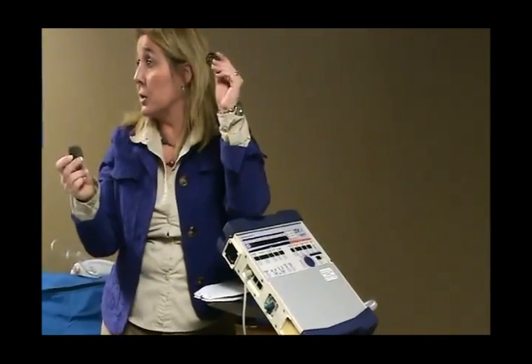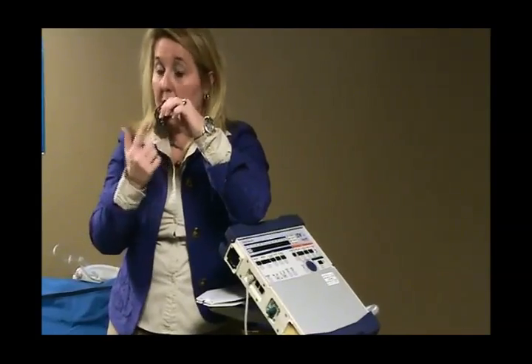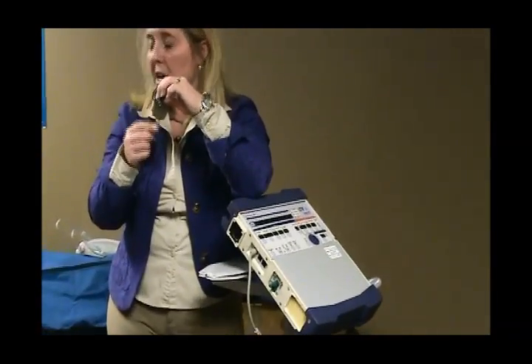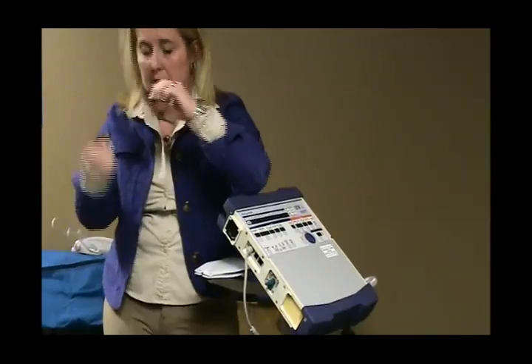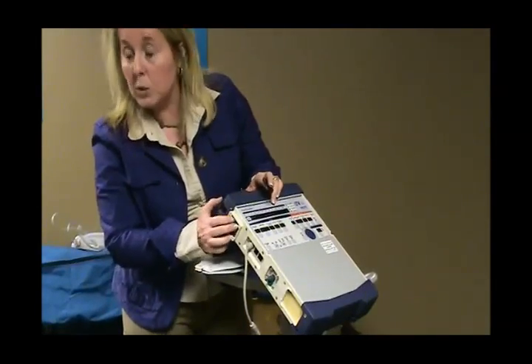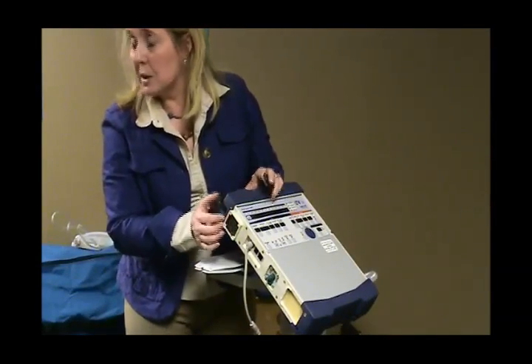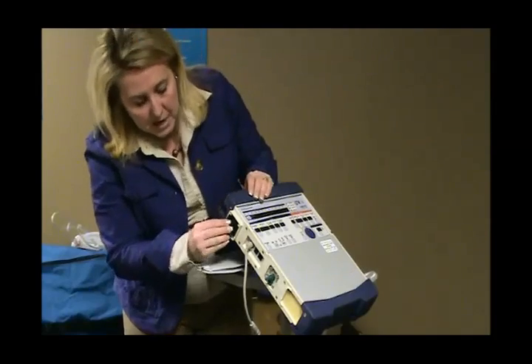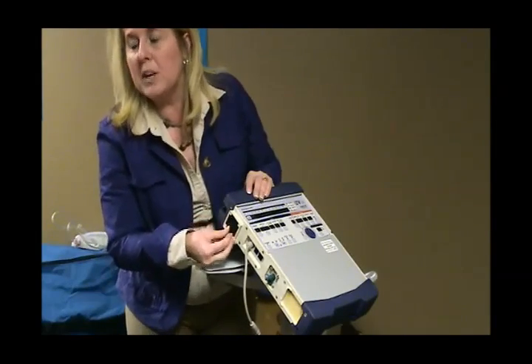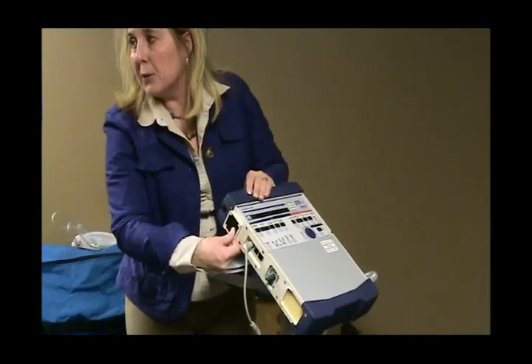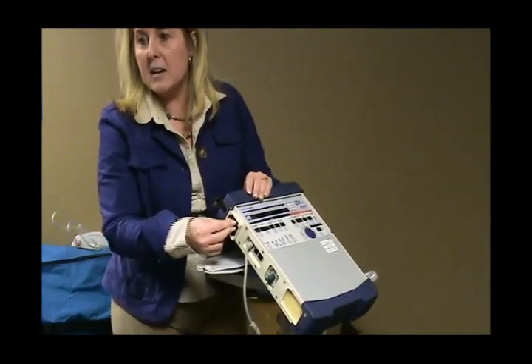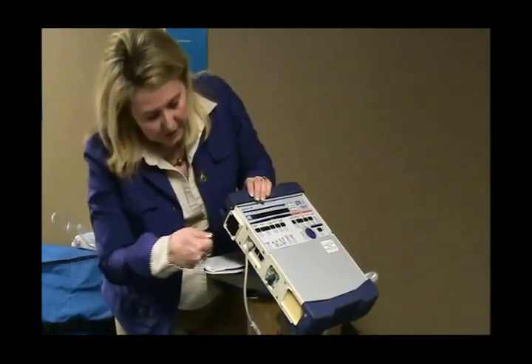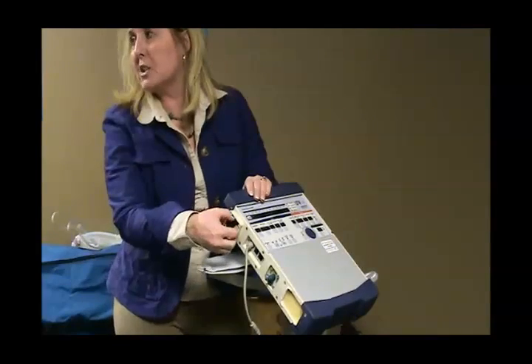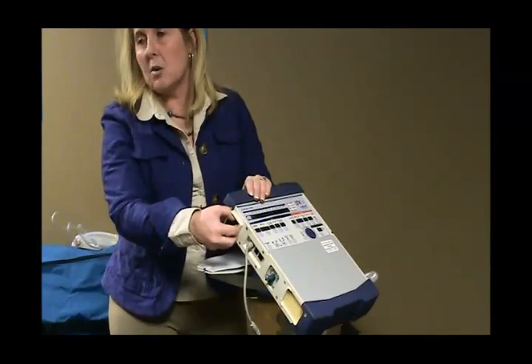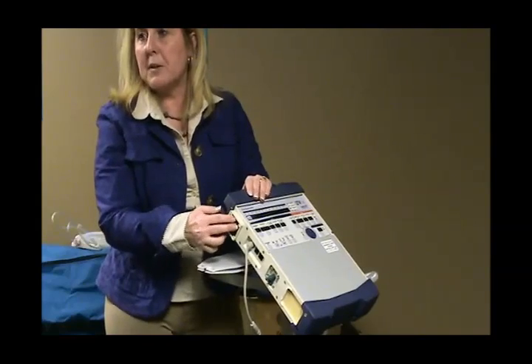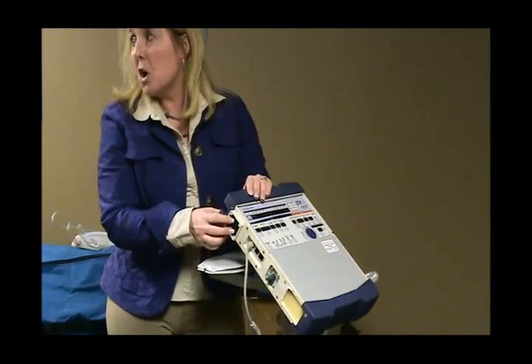Those of you who have been doing this for a while will notice that it eventually gets dust on the outside of it. You just don't want that dust building up too much. You want to keep that clean, so we recommend once a week. In most houses, that'll keep it from causing you a problem. The only thing you need to know is to be careful when you take that out. If you use a hemostat or an ink pen and jam it in there to flip it out, if you touch those fan blades in there, that's a no-no. You will get a message that pops up on the ventilator that says HW fault, hardware fault.